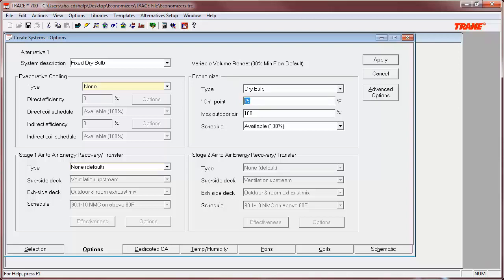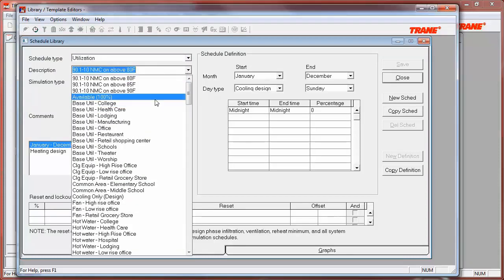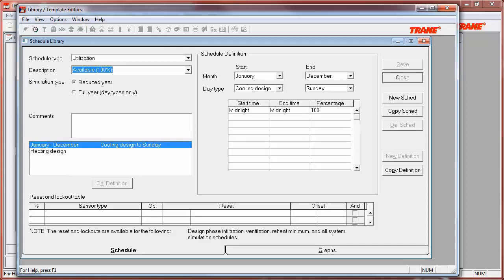Moving on to modeling the differential dry bulb method. This is a bit more complicated, as users will follow the previous methodology with the exception that instead of setting an on point, users will leave that field blank and instead apply a schedule which will include a lockout table. To create the schedule, users will need to navigate to the library template editor and create a new utilization schedule, similar to the default available 100% schedule, with a lockout to ensure the economizer does not operate if the outside air temperature is greater than the return air temperature. For more information on schedule creation, please see our eLearning video titled TRACE 700 Utilization Schedules.